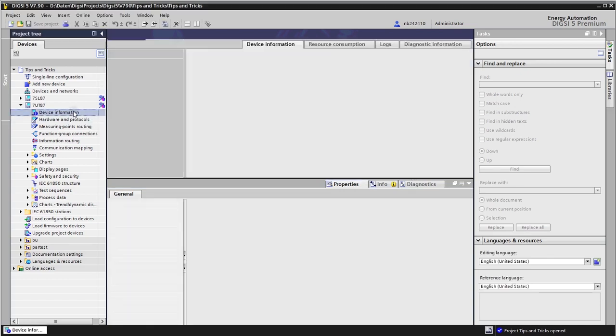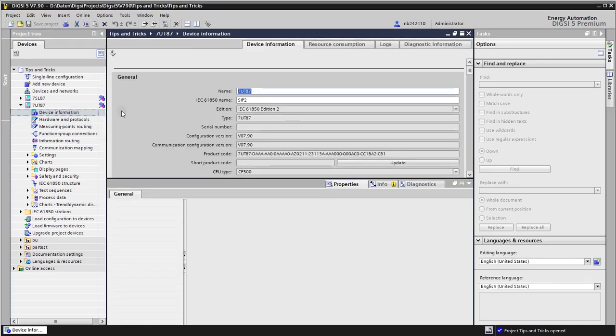Parallel transformer control works only with IEC 61850 edition 2. So let's switch right from the beginning to edition 2 in the device information editor. Here we see the edition and it's already set to edition 2.